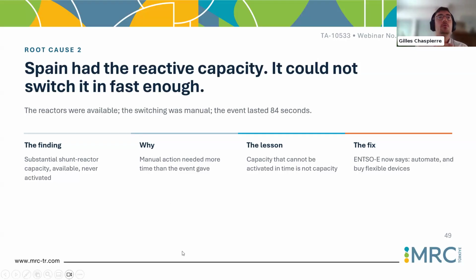Reactors were available, but because the operational process is manual and takes some time, and because of the pre-existing oscillations that unfortunately led the TSO to disconnect some of them, we were in a really bad situation where in 84 seconds there was not enough time to reconnect and make sure that the shunt would be there before the collapse. So they had the capacity, but manual action worsened the situation because, as I said, it is better to have something automatic and fast. Capacity that cannot be activated in time cannot be considered actual reactive capacity, because it's like it's not there. And so now the fix, no surprise, as discussed already: let's automate this. Let's make sure you can monitor the voltage in real time and automatically connect or disconnect the shunt reactor in a limited amount of time.